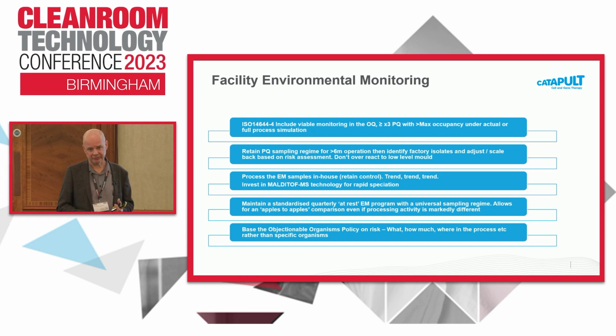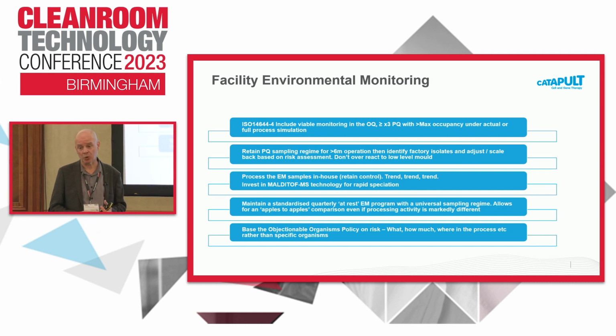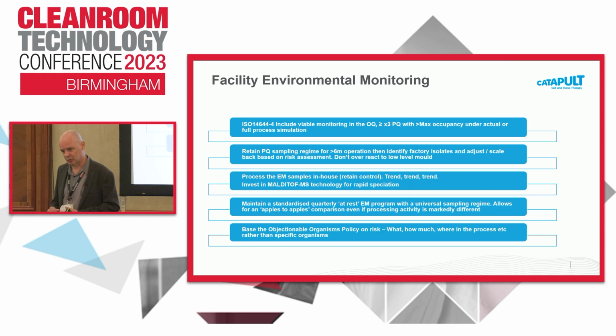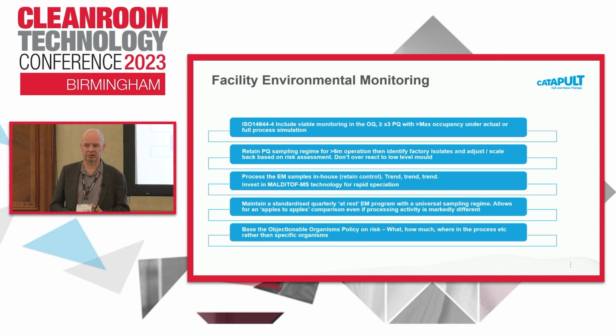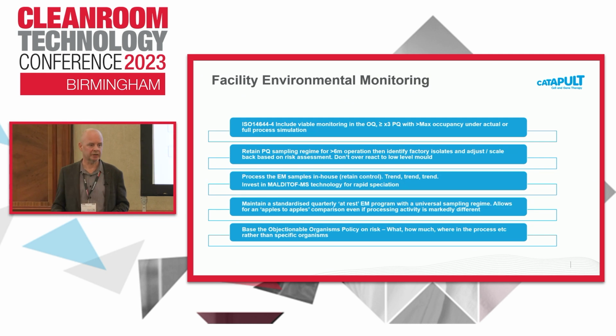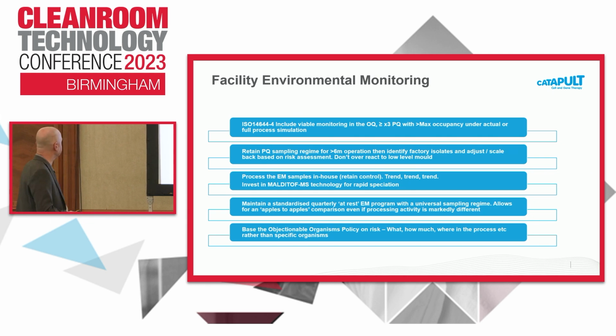My organisation has made good use of the MALDI-TOF MS approach to speciation, and it's phenomenally quick. It's usually a day to subculture and grow up, and then it's a couple of hours on the machine, and you can run 96 samples in a session. So it's far quicker, far easier than sending your samples off to a third party, where you're incurring courier costs. You've got to either pay for a priority service, or you wait your 3, your 5, your 7 days to get your results back. This way, within 24 hours, you've got your EM results processed and your speciation completed. So there are lots of advantages, and it allows a much quicker reaction to any issues that you might find.